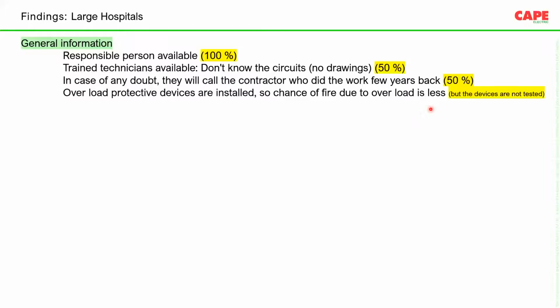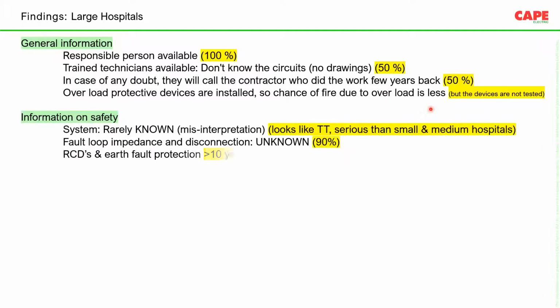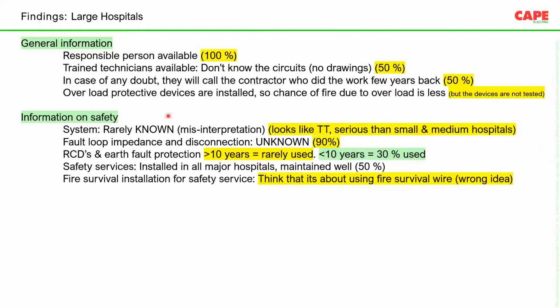But if we ask, are you sure your MCB will trip? Then the problem starts, because this MCB was installed a few years back and nobody knows whether it will work or not. So this is a problem. With respect to safety, the system is rarely known.